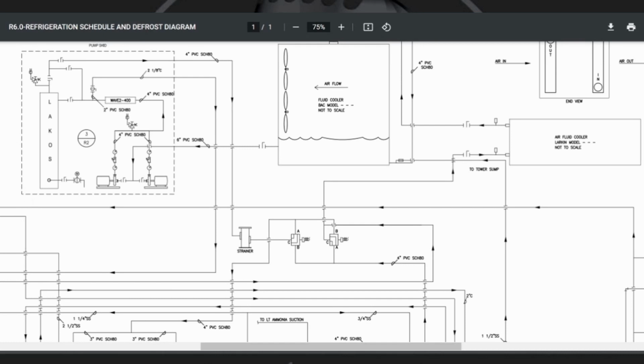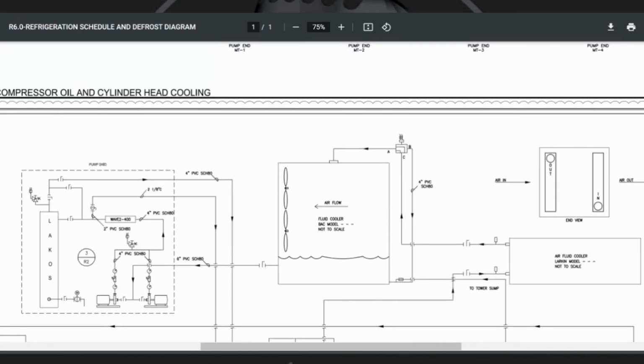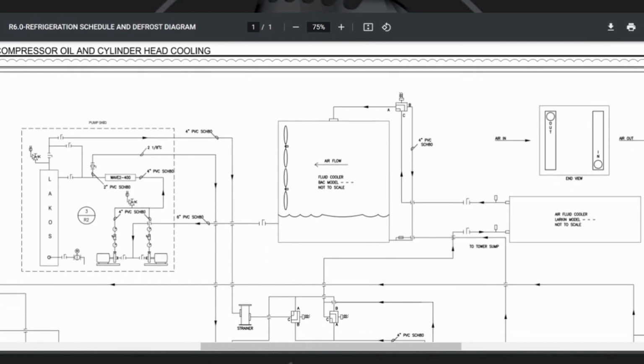How are you maintaining the 400 GPM? Is that done with circuit setters? Are you doing that with VFDs? I mean, how are you figuring out the GPM, or at least setting the GPM? Well, we actually don't. We take whatever we can get. We size the pumps for 400, based on 90-foot head. And then based on the piping and the number of 90s that a contractor puts in or whatever, it might be 400, it might be 380, it might be 410. It doesn't really matter. It's way more than we need.